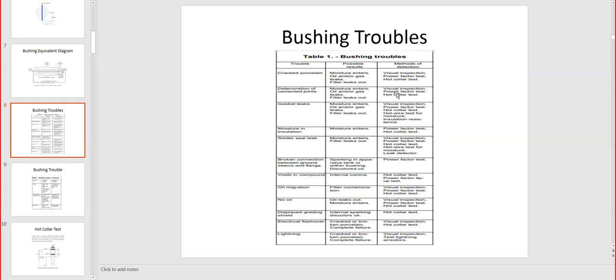So moisture, visual inspection, power factor, hot collar. We continue with gasket. So the bushing is one thing, but then the bushing mounting to the transformer has a gasket that needs to be replaced every 2 years or less, as any material that is non-metal and is deteriorating by aging. Solder or seal leak, broken conductor, voids in compound, oil migration.